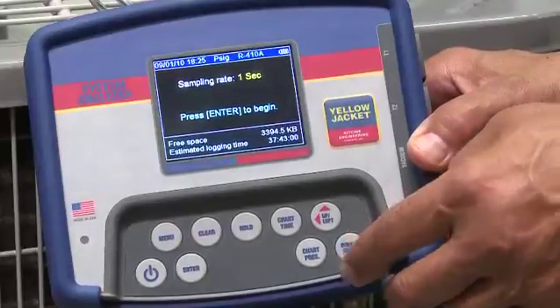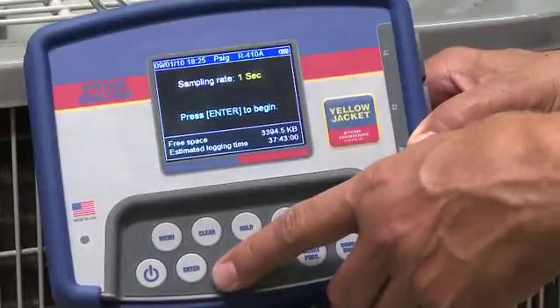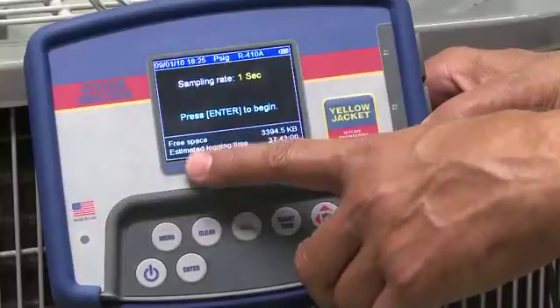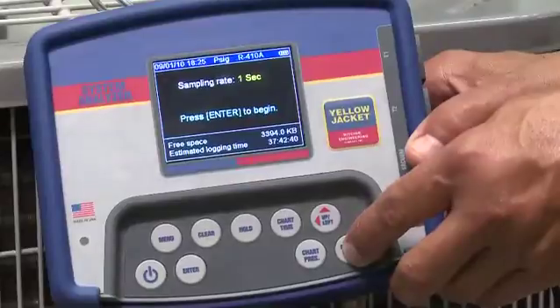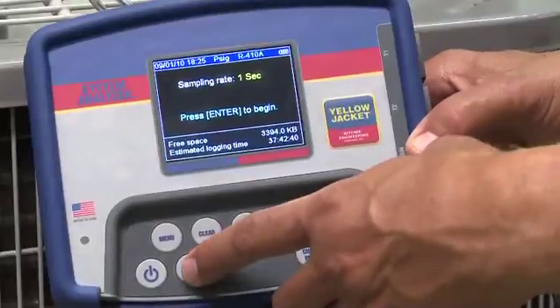You'll notice this screen also lets you know how much memory you have left, as well as the logging time limit. The shorter the time increment, the more data it records and the more memory it requires, so you'll need to monitor this closely. Data logging will stop when the memory is full or the batteries die, so you may also need to clear out old jobs to maximize space. Let's select a sample rate of one second and press Enter to begin.